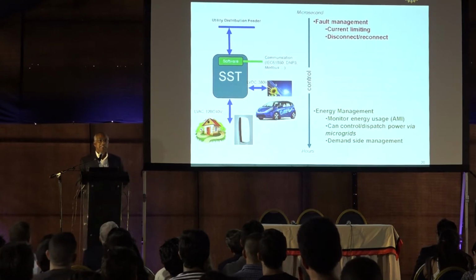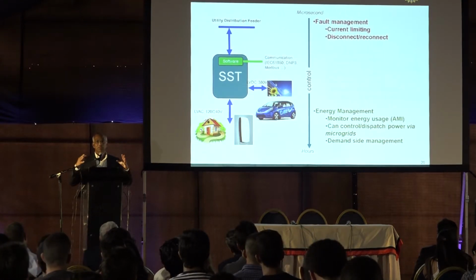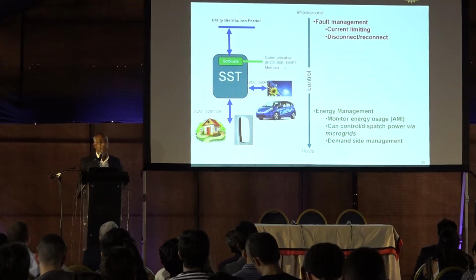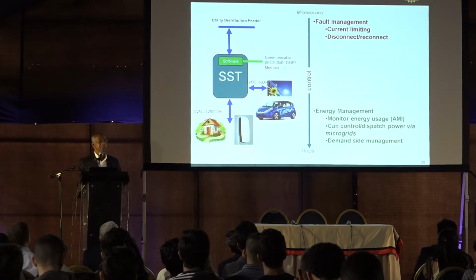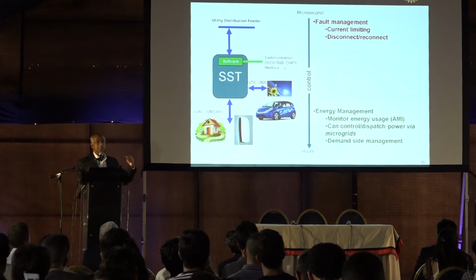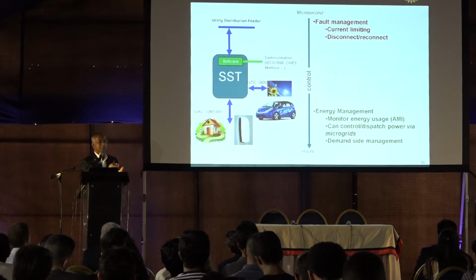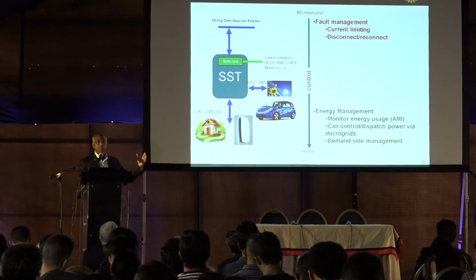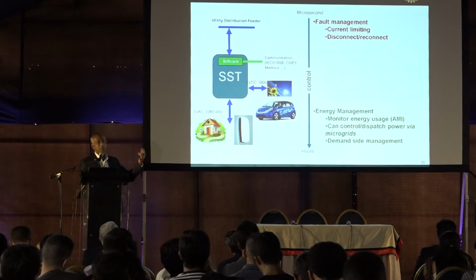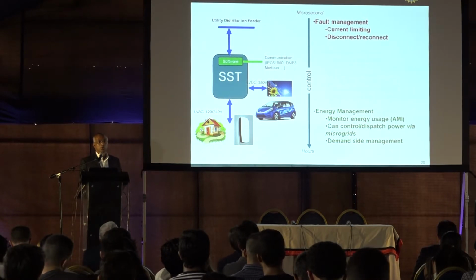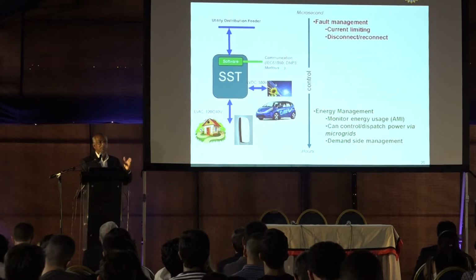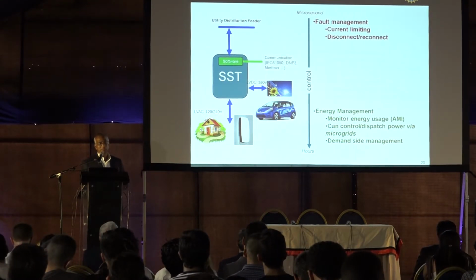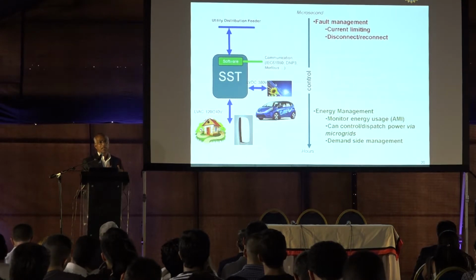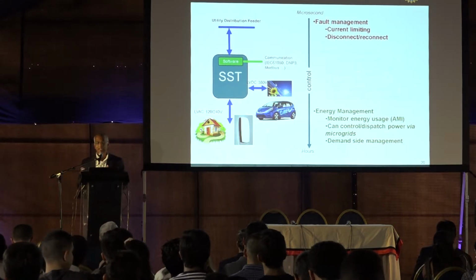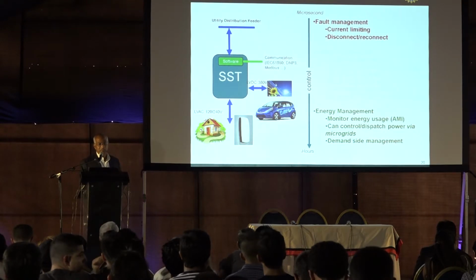So the solid-state transformer, not only being smaller, lighter, compact, gives several other advantages. For example, it is current limiting, in the sense that it can protect itself. It can buffer the system. Like in a traditional transformer, the input and output are fixed by the turns ratio in terms of voltages and currents that flow through. But with this solid-state transformer, you can actually buffer the input side from the output side. It can limit its own current. If there is a fault on one side, it can isolate that fault. It can quickly connect or disconnect.